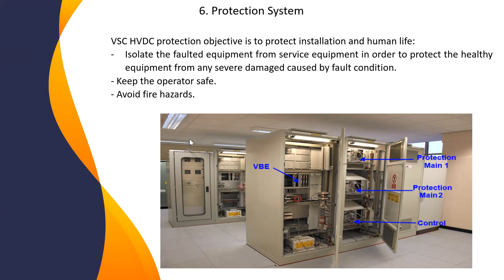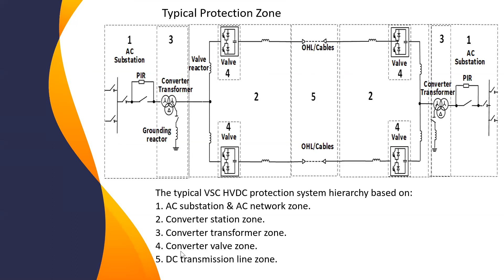So when we are talking about protection, we are talking about protection zone. The same for AC. Actually, in HVDC, this is the typical protection zone here. So for instance, we can have zone 1 only to protect AC, and then zone 2 to protect converter station, zone 3 to protect converter transformer, and then zone 4 to protect only valve, and zone 5 to protect all overhead line or cable. Once again, this is only typical zone protection. Can be 5 zones, can be 6 zones, depending on the design here.